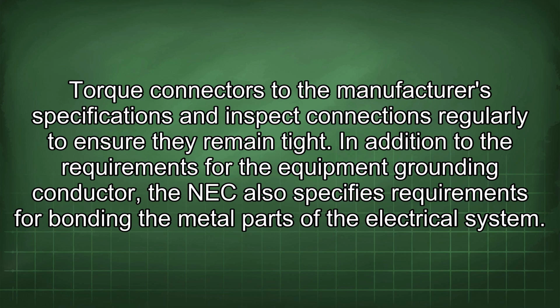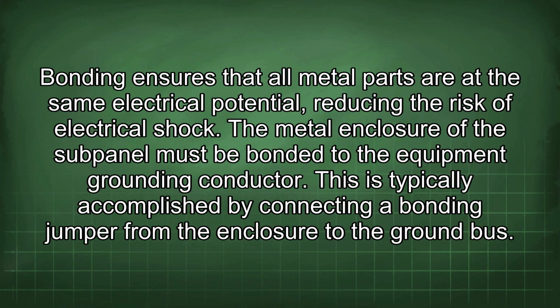In addition to the requirements for the equipment grounding conductor, the NEC also specifies requirements for bonding the metal parts of the electrical system. Bonding ensures that all metal parts are at the same electrical potential, reducing the risk of electrical shock. The metal enclosure of the subpanel must be bonded to the equipment grounding conductor. This is typically accomplished by connecting a bonding jumper from the enclosure to the ground bus.